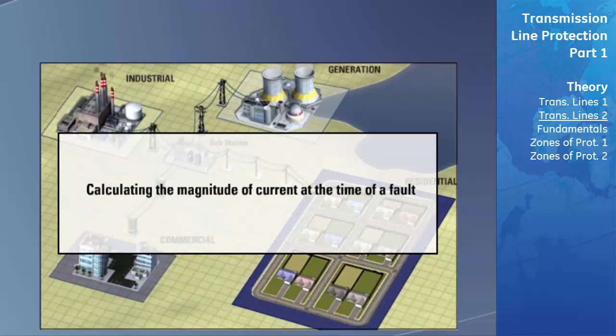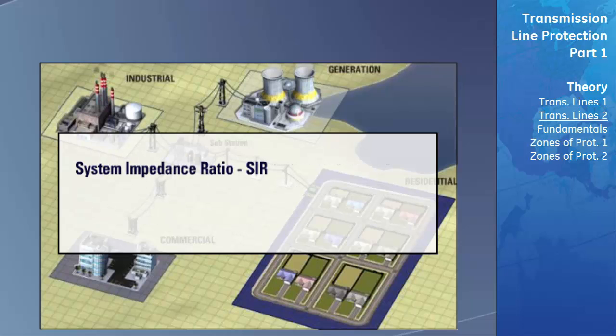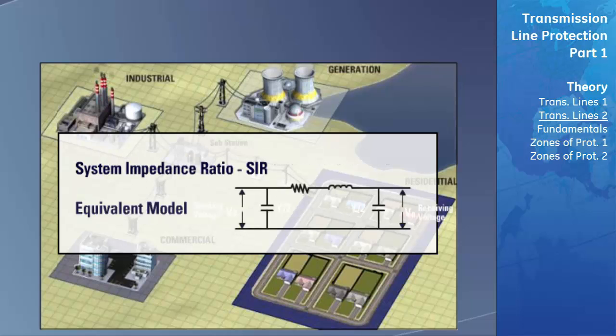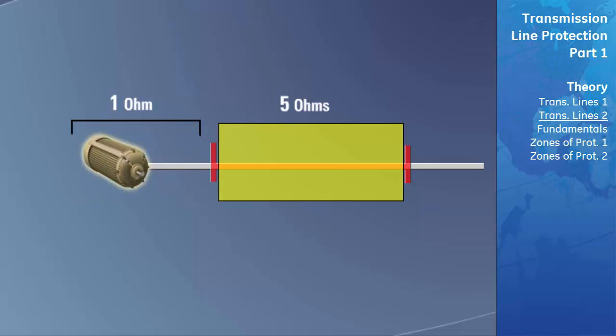Calculating the magnitude of current that will flow through the transmission line at the time of the fault and configuring accurate settings for distance relays is a very important task that the protection engineer must perform. In order to do this, the protection engineer must first calculate the system impedance ratio and develop an equivalent electrical model of the transmission line. The system impedance ratio is a factor that needs to be considered when determining how to protect the transmission line and can greatly affect what will happen to a power system at the time of a fault. The system impedance ratio takes the source impedance of the system behind the transmission line and divides that by the line impedance that is being protected.